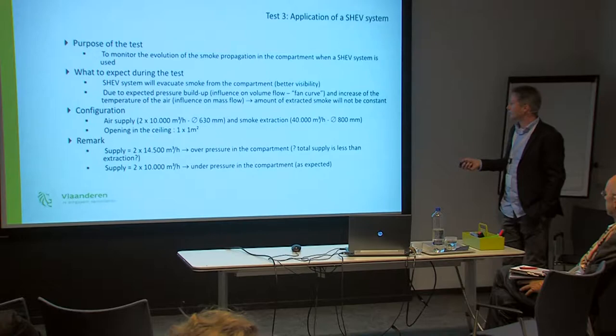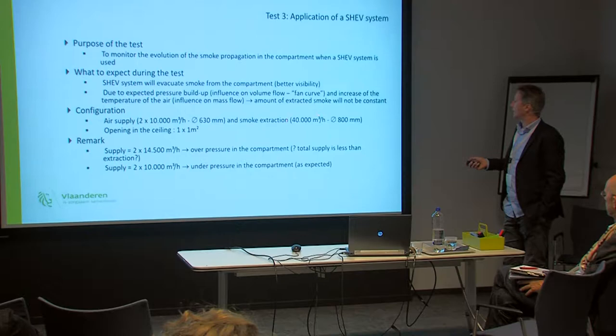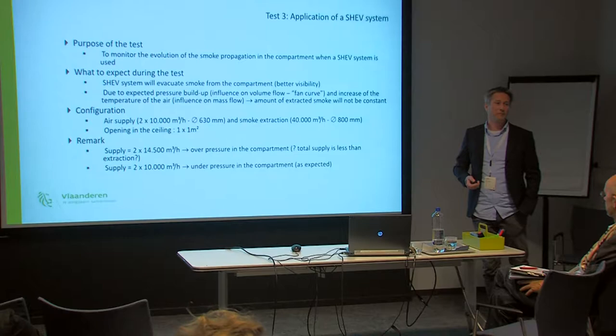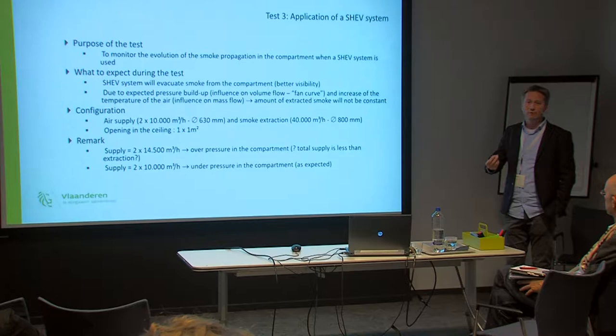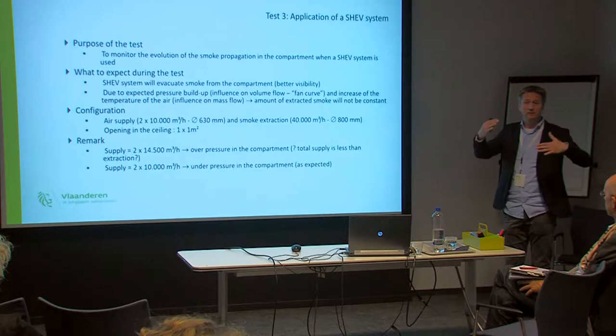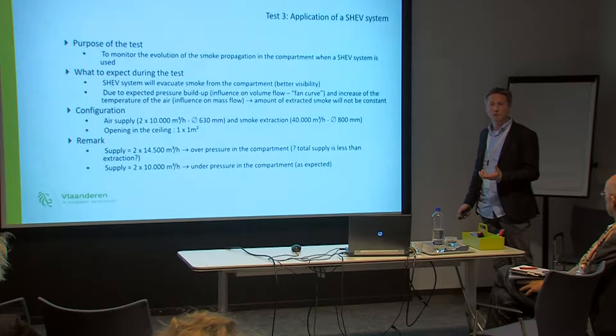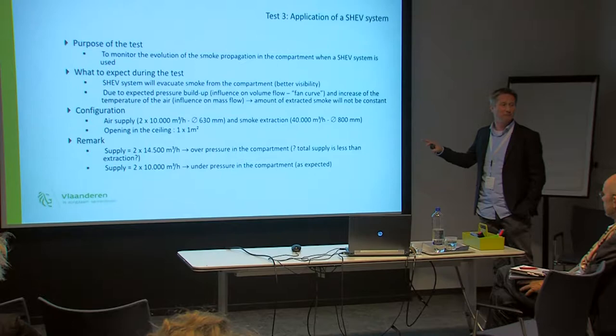Just one remark. In the beginning, we used two air supplies of 14,500. We have 40,000 extraction. You assume you have under pressure. We had overpressure. Before the test, of course. So this is my personal opinion. I think that in a confined room, you have the influence of your pressure on your extraction and your air supply, and they go sort of equivalent. But at the end, we did 2 times 10,000, meaning 20,000 supply and 40,000 extraction, and then we had under pressure. So confined rooms and mechanical extraction and supply, tricky, tricky.